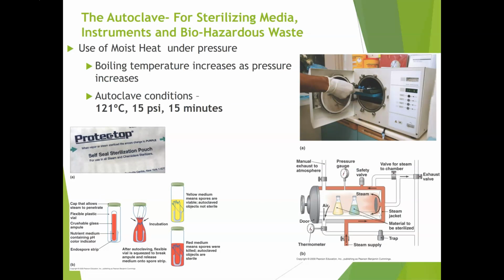The autoclave is an essential piece of equipment for any laboratory, including a cell culture lab. This instrument is used to sterilize instruments and glassware, media or buffers without heat-sensitive components, and biohazardous waste. The autoclave is basically a large pressure cooker. The chamber must reach 121 degrees Celsius. It uses steam under 15 pounds per square inch (psi) of pressure, and this condition is held for a minimum of 15 minutes to ensure sterility.